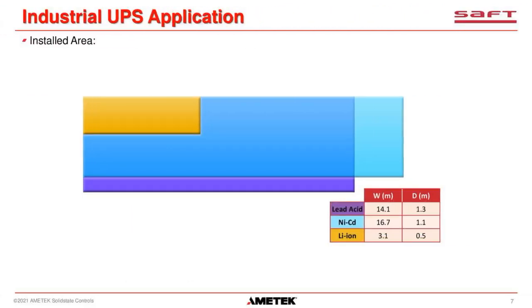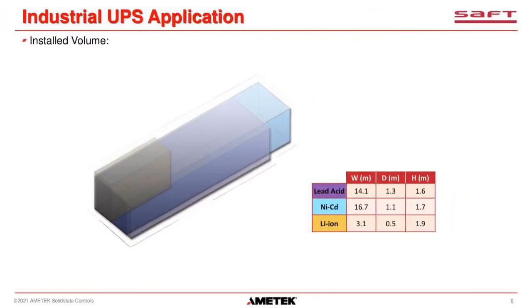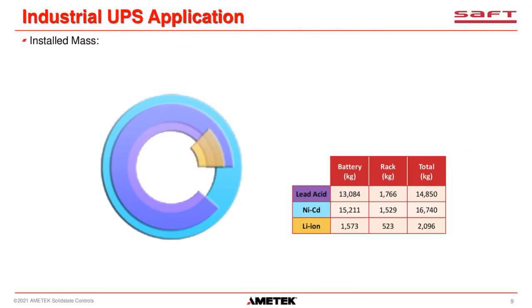The advantage of a lithium-ion battery compared to lead acid and NiCad is that the footprint is much smaller than those two. You can see in this image that it's about 20% of the size of a lead acid battery. The installed volume is also much lower with lithium. You can see here the lithium is the yellowish brown box there compared to lead acid and NiCad. And the last advantage as far as size goes is that the mass of the lithium-ion batteries is much, much less than both NiCad and lead acid.